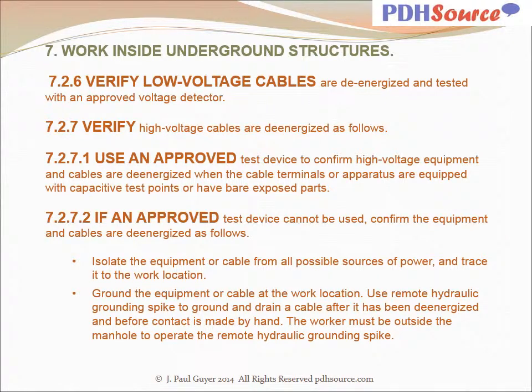Verify low voltage cables are de-energized and tested with an approved voltage detector. Verify high voltage cables are de-energized as follows. Use an approved test device to confirm the high voltage equipment and cables are de-energized when the cable terminals or apparatus are equipped with capacitive test points or have bare exposed parts. If an approved test device cannot be used, confirm the equipment and cables are de-energized as follows. Isolate the equipment or cable from all possible sources of power and trace it to the work location. Ground the equipment or cable at the work location. Use remote hydraulic grounding spike to ground and drain a cable after it has been de-energized and before contact is made by hand. The worker must be outside the manhole to operate the remote hydraulic grounding spike.